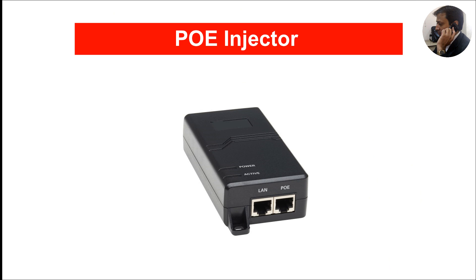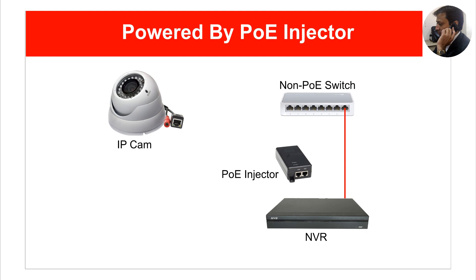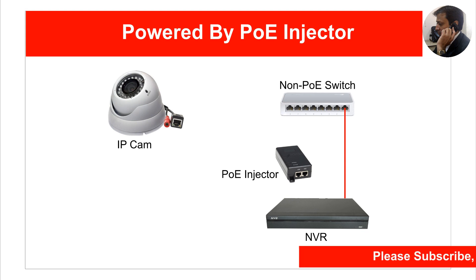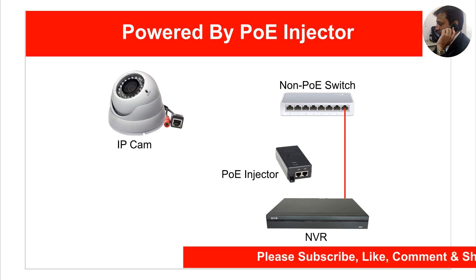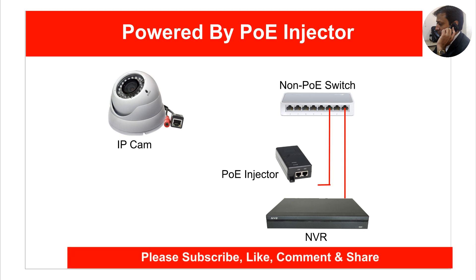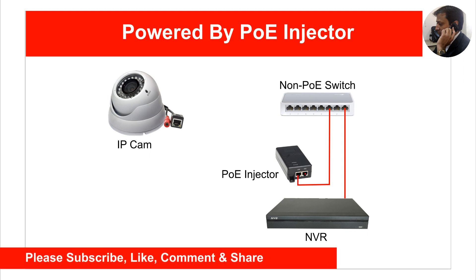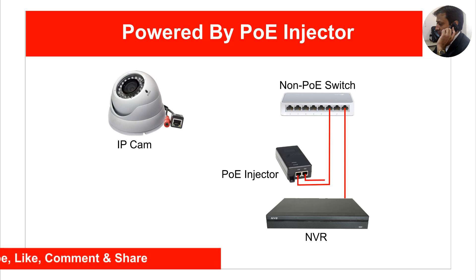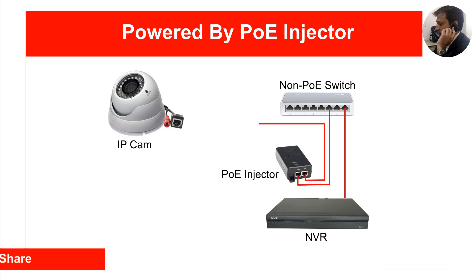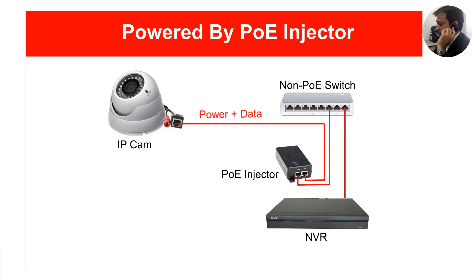The last method we will discuss is the use of a PoE injector. A PoE injector is similar to a PoE splitter, but the only difference is that the injector has an inbuilt DC power source. Similar to the PoE splitter, it also combines power and data to enable it to run on a single ethernet cable, eliminating the need to run an additional cable to provide power to the camera.